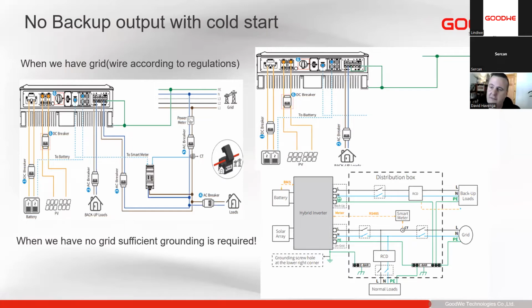It's for safety of the product, for safety of the customers. We always need to make sure that there is grounding, because we're creating grid here, we're creating a thing that has potential to cause a shock. So everything needs to be grounded. Even if you create your own grounding network at the site, the body of the inverter needs to be grounded, as well as the terminals of the inverter needs to have that ground connected. Otherwise, the inverter might not start at all because it detects there is no ground. So please always refer to the installation manuals. If there's no grid, you can ignore the live and neutral, but the grounding always needs to be there.